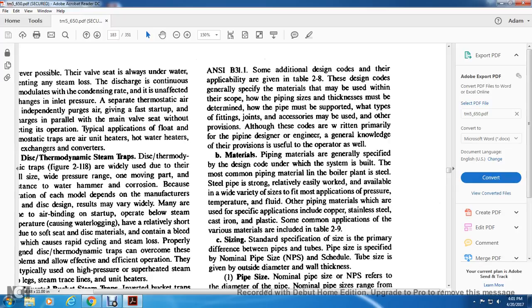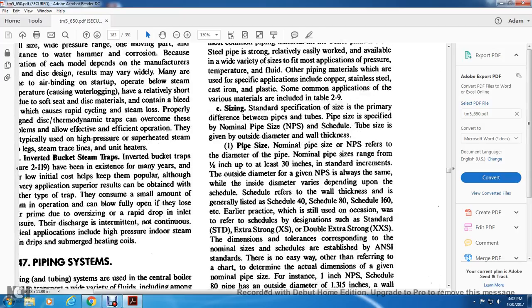Materials. Piping materials are generally specified by the design code under which the system is built. The most common piping material in the boiler plant is steel. Steel piping is strong, relatively easily worked, and available in a wide variety of sizes for most applications of pressure, temperature, and fluid. Other piping materials are used for specific applications, including copper, stainless steel, cast iron, and plastic, and some common applications with various materials are included in Table 2.9.